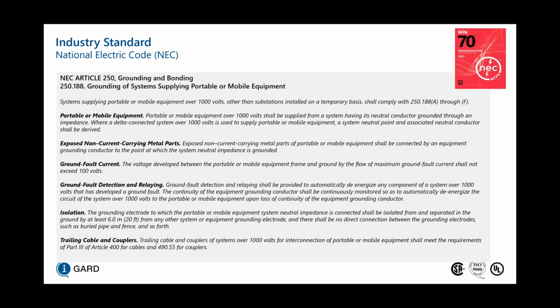For ground fault detection and relaying, there's a requirement to detect faults as well as monitor the continuity of the ground loop and the grounding conductor. And isolation is also important in terms of the grounding electrodes for portable or mobile equipment. They should be separated by at least 6 meters from any other system or equipment grounding electrode. And that way we can reduce the impact of that ground potential rise that occurs at the point of fault.